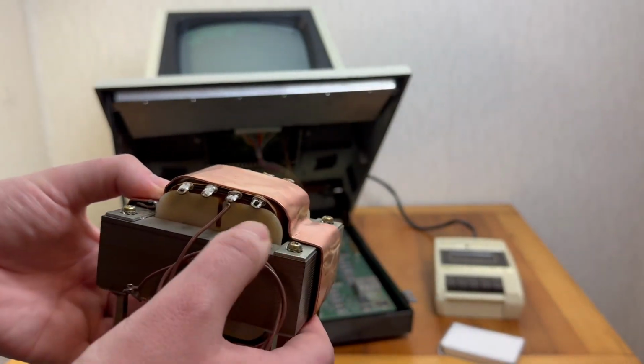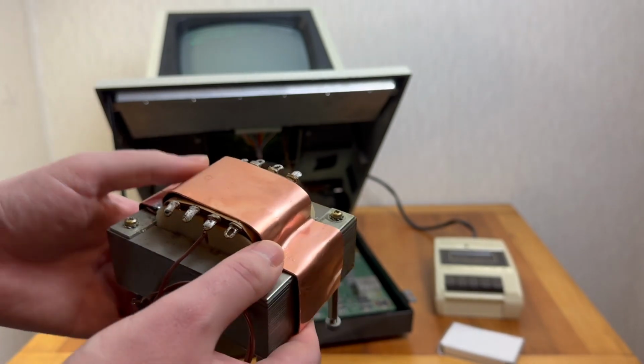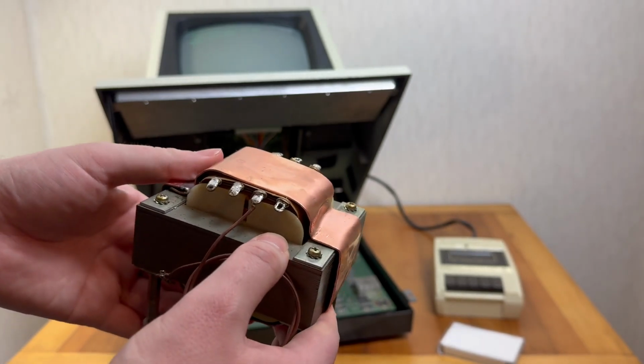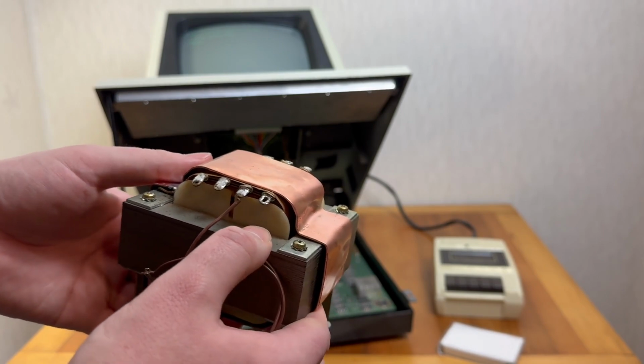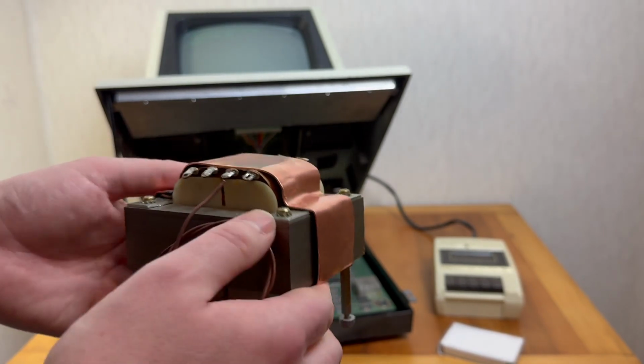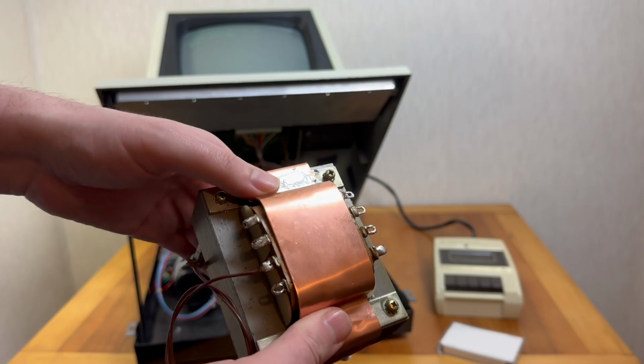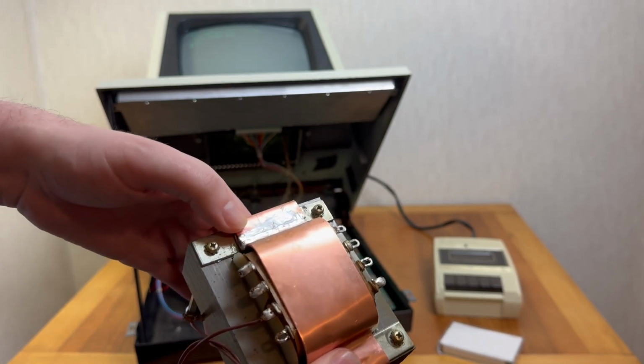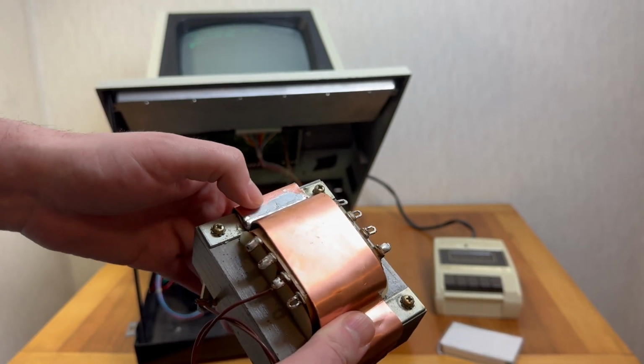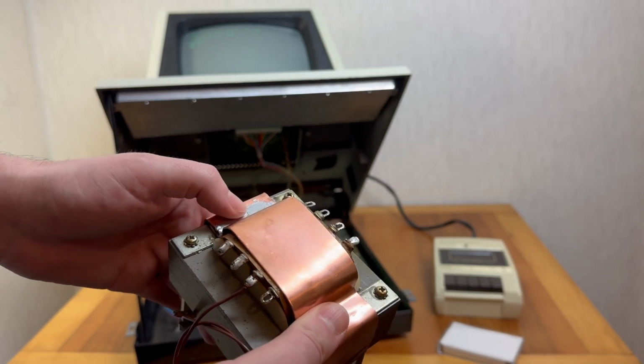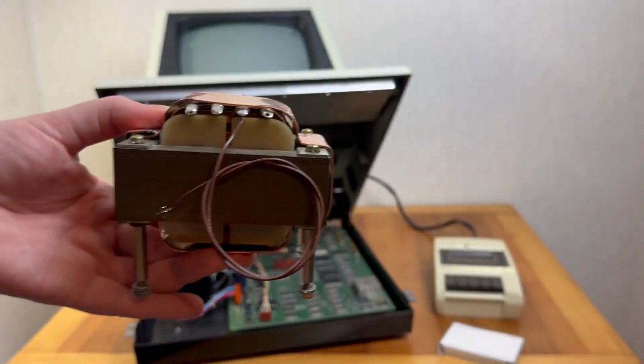The recommendation is 0.6 to 0.8 millimeters, and knowing that the lower the frequency, the thicker the copper band needs to be, I went ahead and installed a 1mm band here. It's important that you solidly solder it, which took quite a lot of effort on a large transformer with a 1mm copper band surrounding it. But eventually I did get a good electrical connection and reinstalled this in the machine.